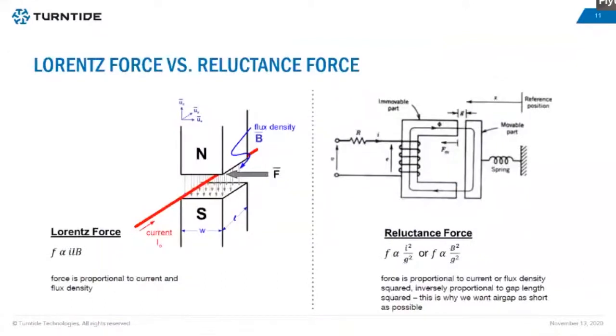Just to give you an idea about the fundamental difference between induction motors, permanent magnet motors, and switched reluctance motors: the foundation is how the mechanical force is generated. In induction motors or permanent magnet motors, the force is generated based on the Lorentz force, which we call the BLI force. B means magnetic flux density, L means length of the conductor, and I is the current through that conductor. So in permanent magnet motors or induction motors, you need a source of magnetic field and a current carrying conductor in that magnetic field to produce a Lorentz force, and that force is converted into torque.